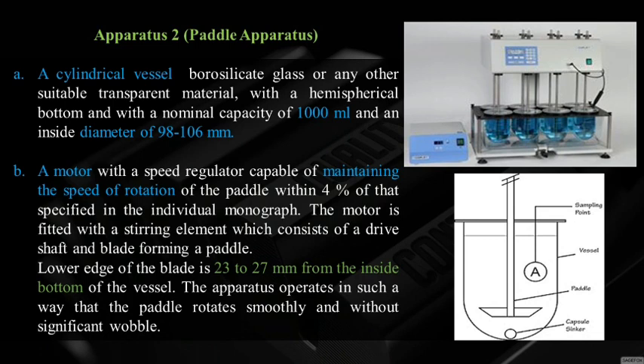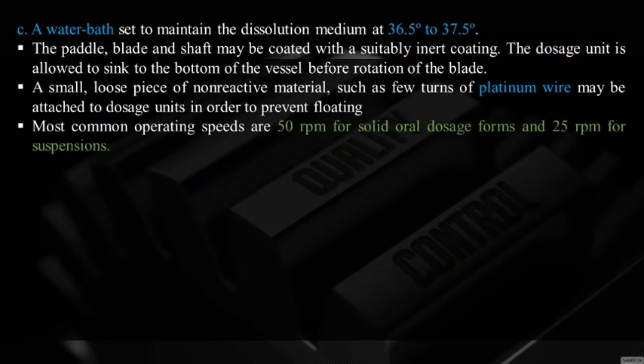Apparatus 2 — Paddle Apparatus: similar cylindrical vessel with capacity 1000 mL and internal diameter 98 to 106 mm. Speed of rotation maintained within 4% of the specified value. The motor is fitted with a driven shaft and blade forming a paddle. The lower edge of the blade is 23 to 27 mm from the inside bottom of the vessel. The apparatus operates so the paddle rotates smoothly without significant wobble.